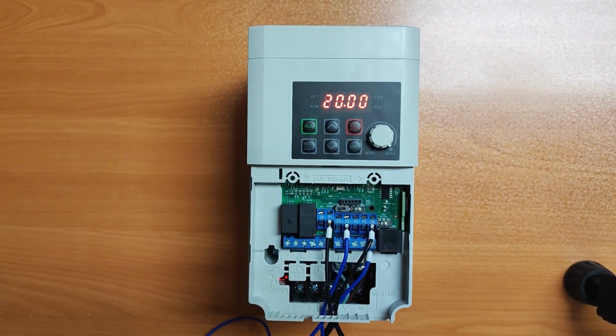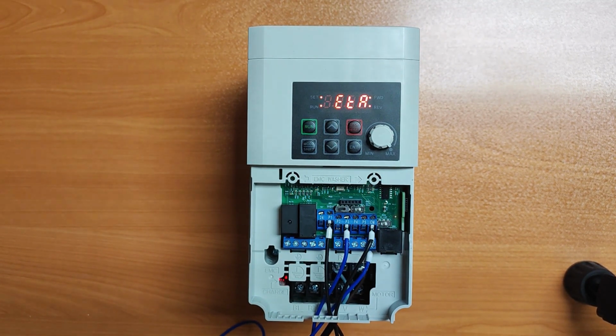Now, I'll start the inverter. My inverter starts up. Now, if I activate my 0-1 switch, you'll see the external trip fault appear on the inverter. Now, if I deactivate the 0-1 switch and my fault is cleared, 3 seconds later, the inverter should start automatically.